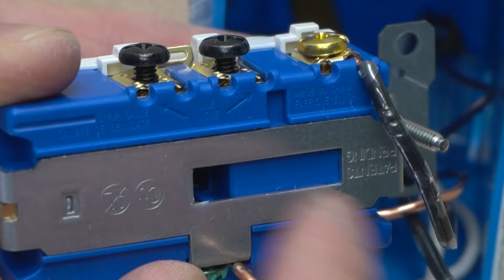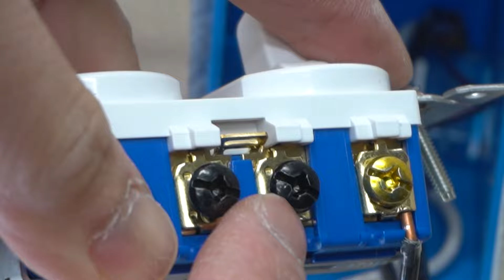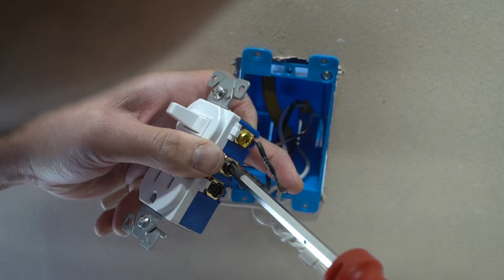Lastly, we are going to do the hot line. We're going to take this label off, cut that off. Now if you look at the very back of these two black terminals, you can see it's labeled line, so it doesn't really matter which one you put the hot wire onto. The only thing that matters is if you want to control this independently with a light switch, then you can take off and break off this tab right here. But in this case, we're going to keep that connected, so either one of these will work. We can connect the hot to any of these.